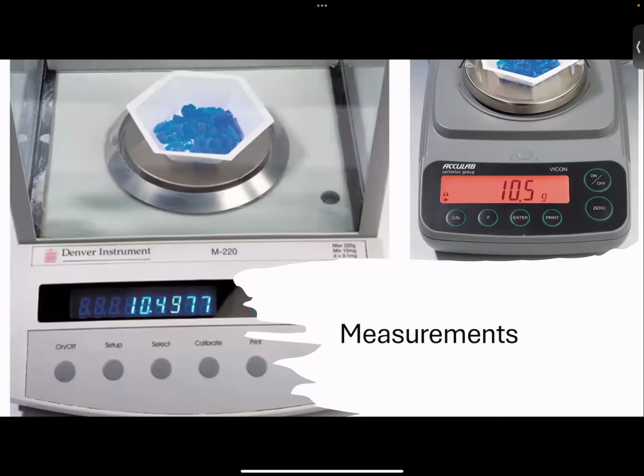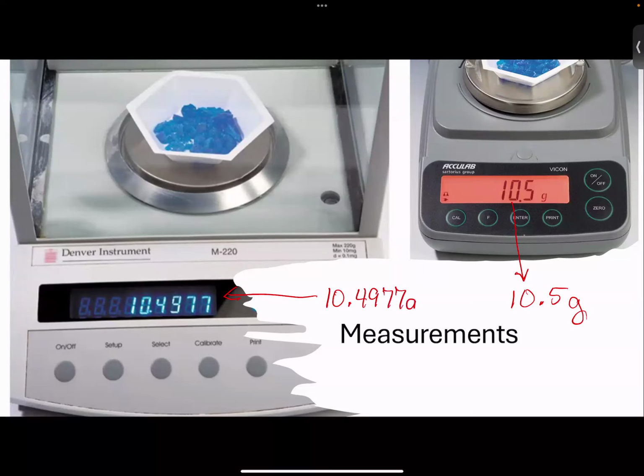So let's look at these two. This top right one, if I record it, I would record it as 10.5 grams because it's digital. I record what I can see. This other one, if I record it, I'm going to record 10.4977 grams because it's digital. I'm going to record what I can see.